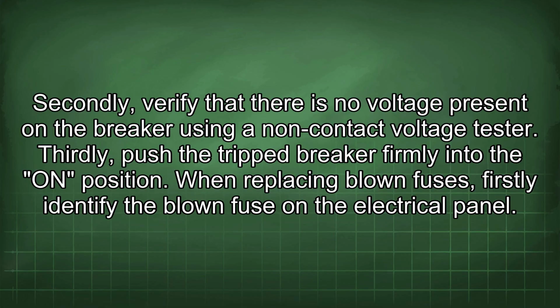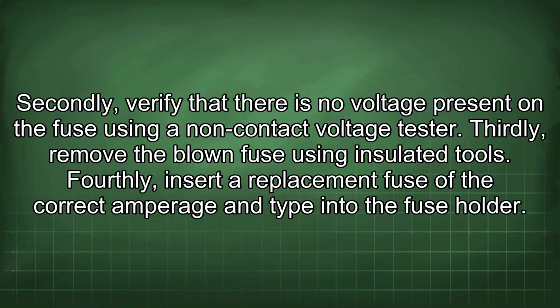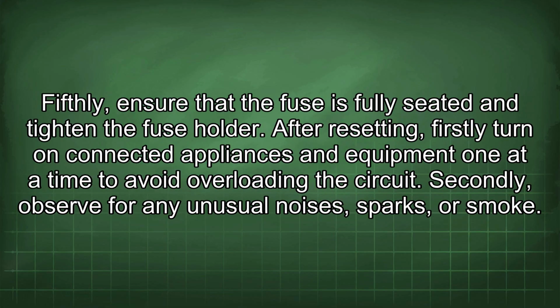When replacing blown fuses, firstly identify the blown fuse on the electrical panel. Secondly, verify that there is no voltage present on the fuse using a non-contact voltage tester. Thirdly, remove the blown fuse using insulated tools. Fourthly, insert a replacement fuse of the correct amperage and type into the fuse holder. Fifthly, ensure that the fuse is fully seated and tighten the fuse holder.